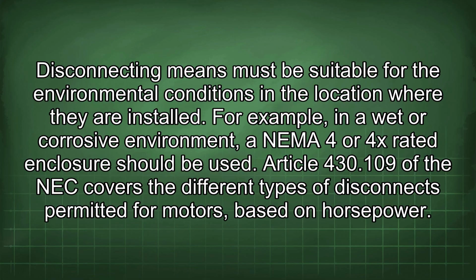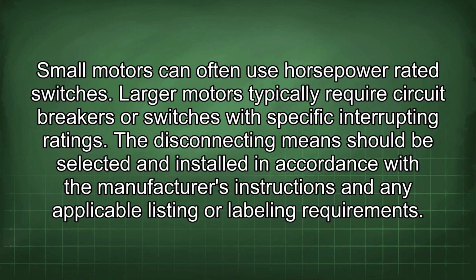Article 430.109 of the NEC covers the different types of disconnects permitted for motors, based on horsepower. Small motors can often use horsepower-rated switches. Larger motors typically require circuit breakers or switches with specific interrupting ratings. The disconnecting means should be selected and installed in accordance with the manufacturer's instructions and any applicable listing or labeling requirements.